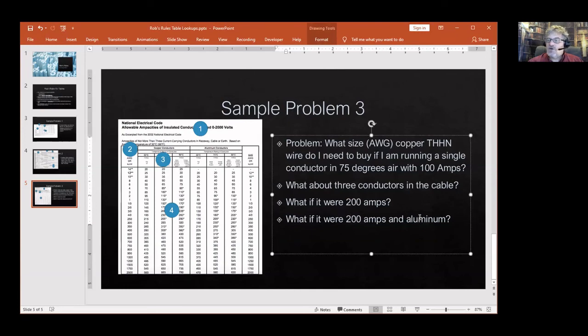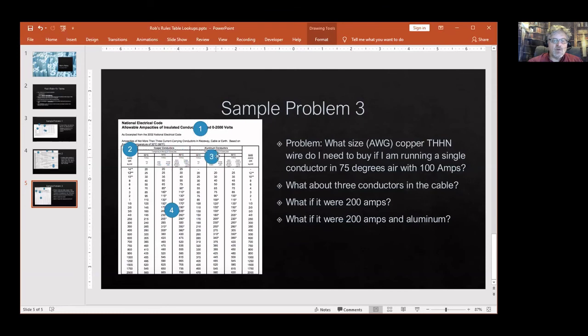What if we're 200 amps and I chose aluminum wire? Oh aluminum, well I'm on the wrong column because aluminum is on the right side of this table so I'd slide that over to where THHN is in the aluminum. And now I'm talking at 200 amps. I don't have a 200 amps in aluminum so how do I solve this? I round up.